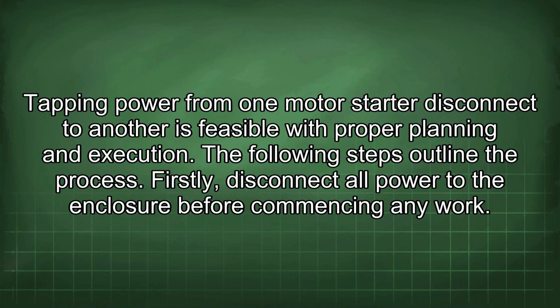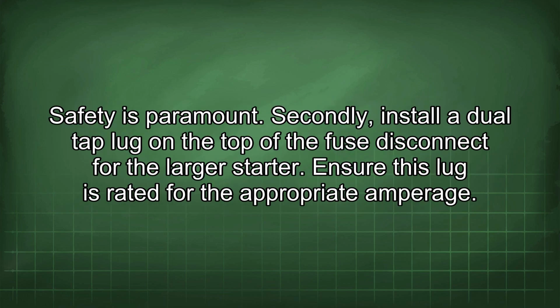Tapping power from one motor starter disconnect to another is feasible with proper planning and execution. The following steps outline the process. Firstly, disconnect all power to the enclosure before commencing any work. Safety is paramount. Secondly, install a dual tap lug on the top of the fuse disconnect for the larger starter. Ensure this lug is rated for the appropriate amperage.